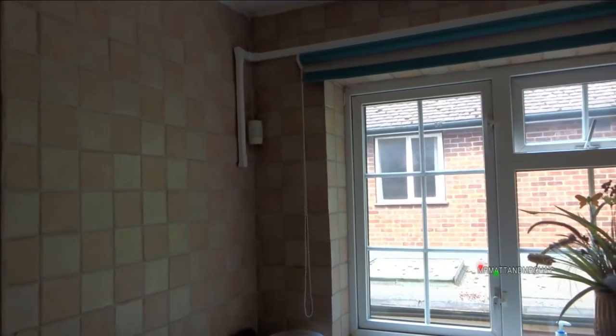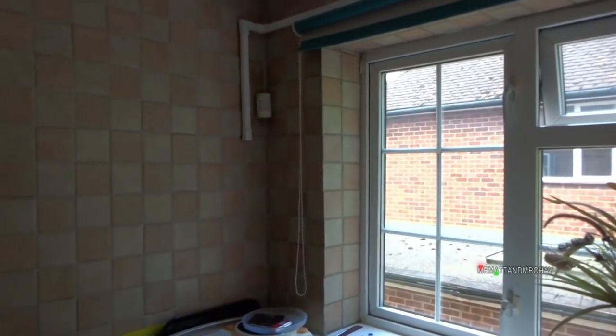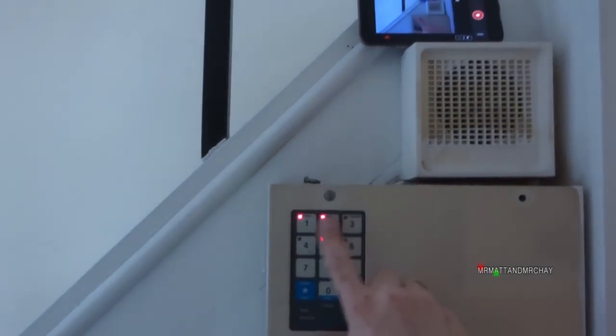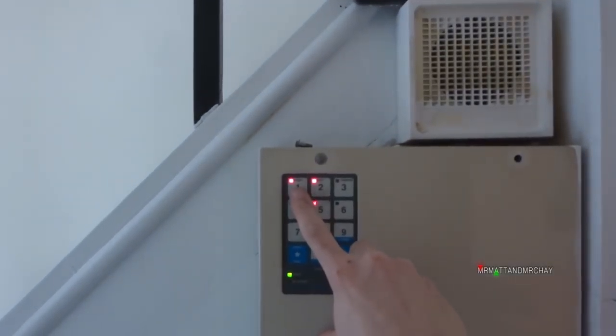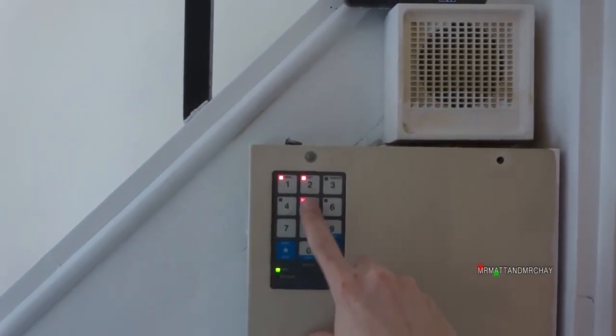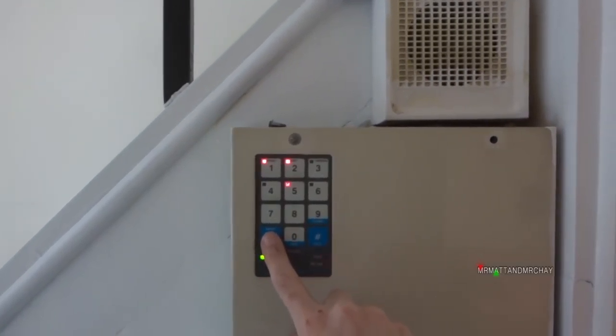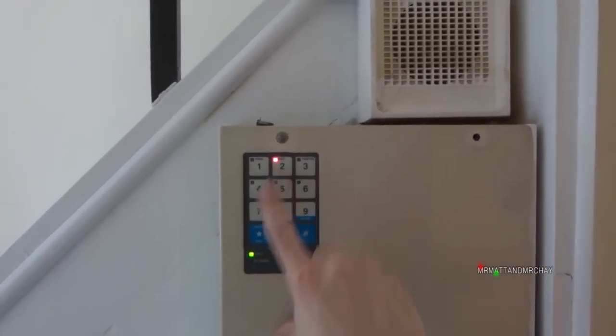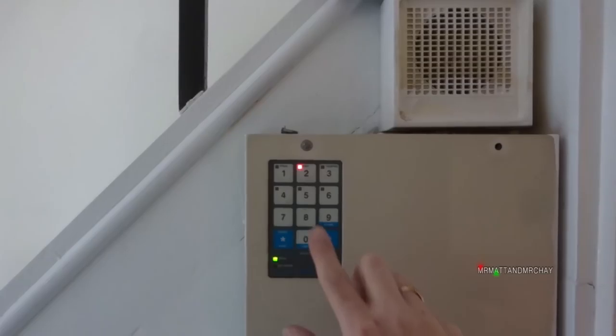Activate the detector. Zone 1, Zone 2 and Zone 5 activated. To find the first one, you press reset. First zone to activate was Zone 2. Then you just set it as normal for next time.